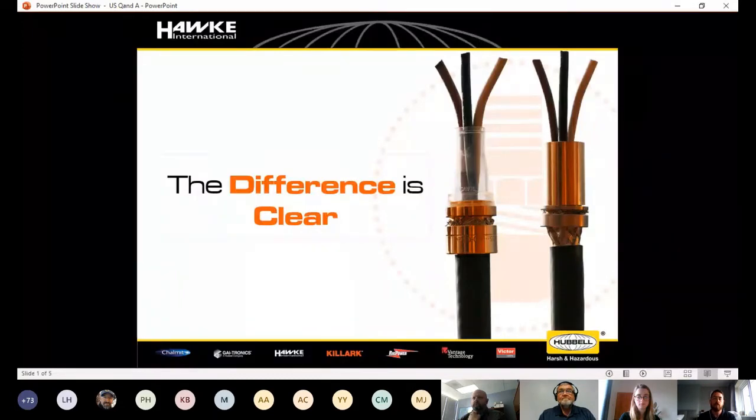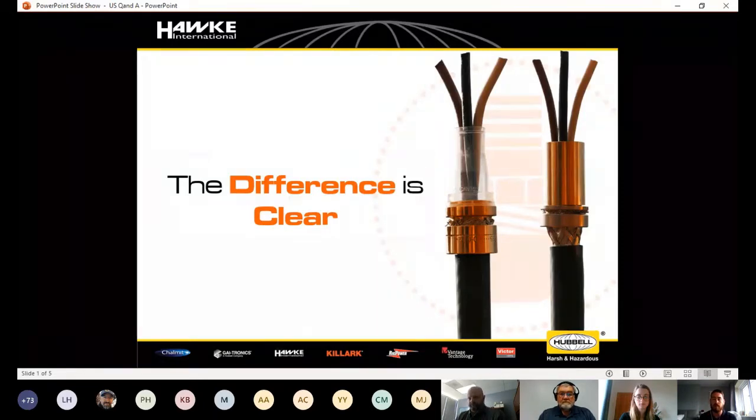Removing that compound chamber off of the epoxy liquid putty was not really a viable option. So that's when we started to look at see-through materials, and the clear silicone compound pot is where we pushed, and pushed for certification to get that over the line. And obviously the inspectability aspect of it: you can see as you're pouring, and you can ensure that it has been installed correctly first time, every time. As the material flows around all of the cores, it fills up. It's night and day between the black compound that we supply and the clear resin, so you can easily see that it's been filled properly.